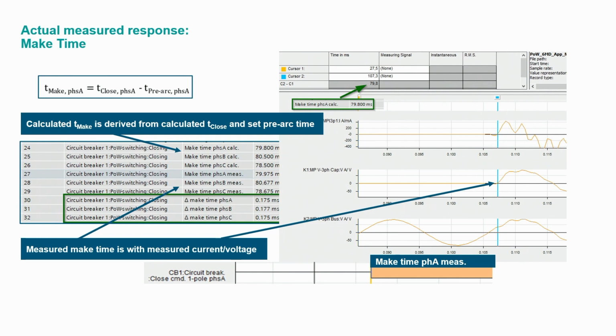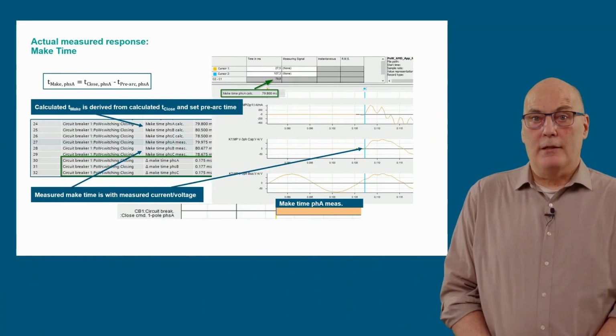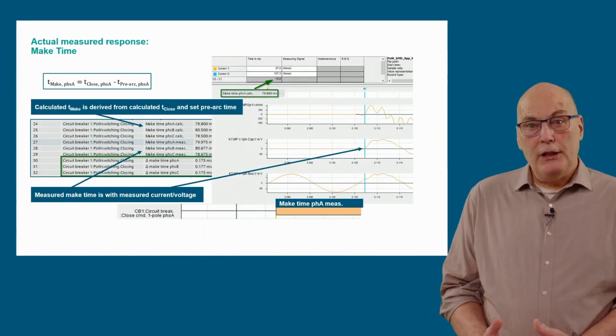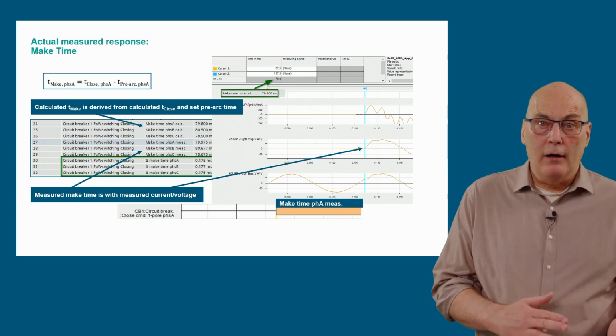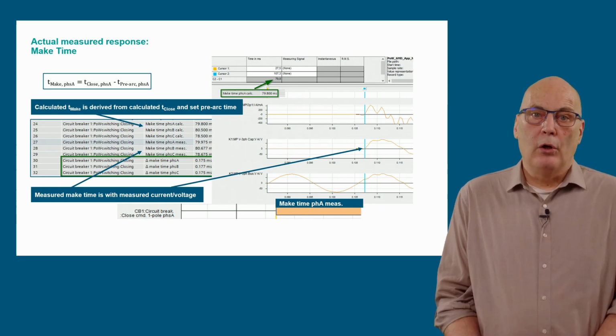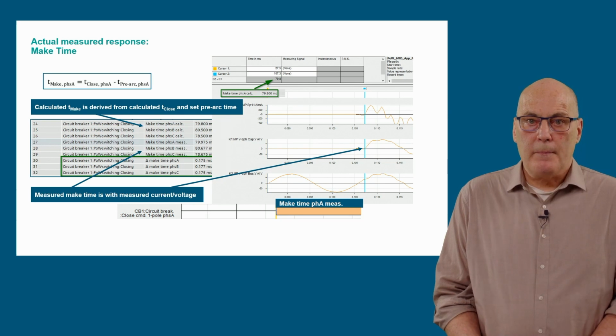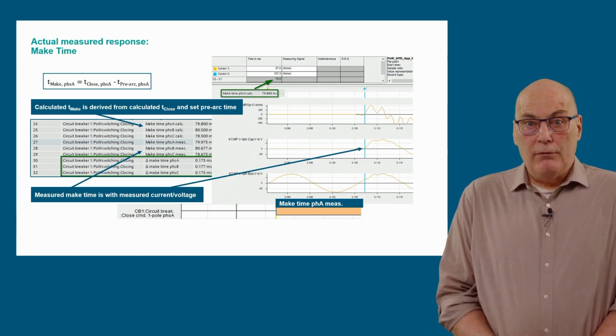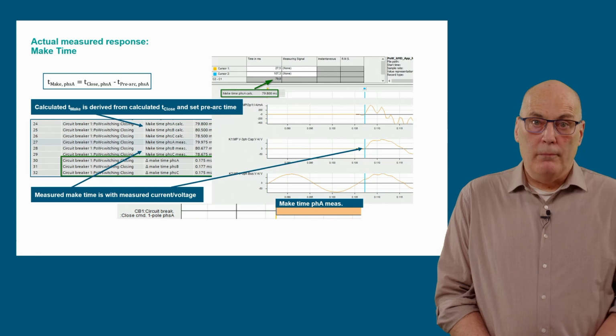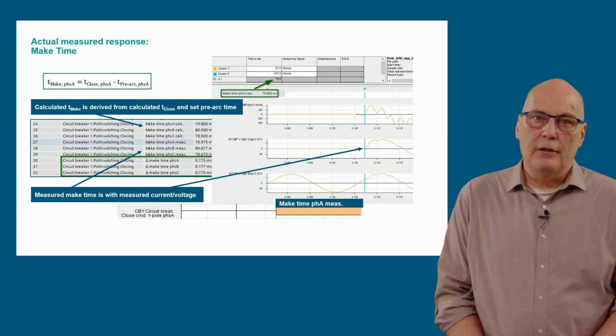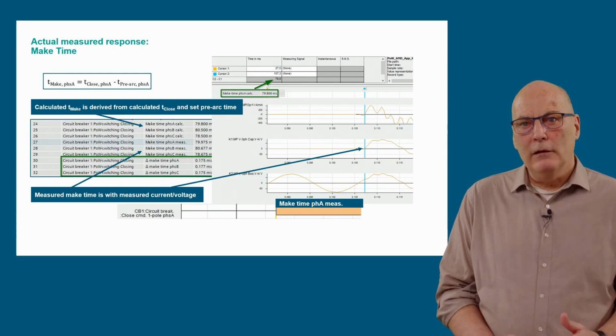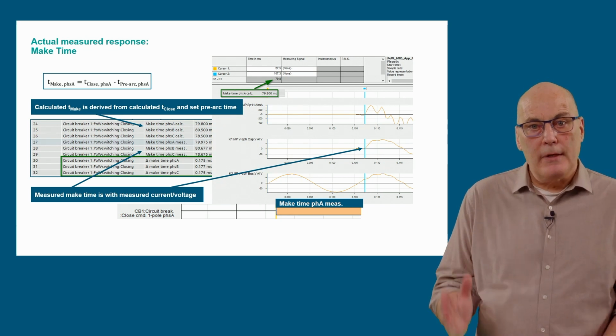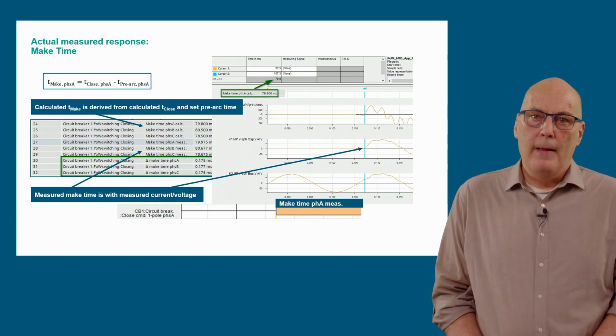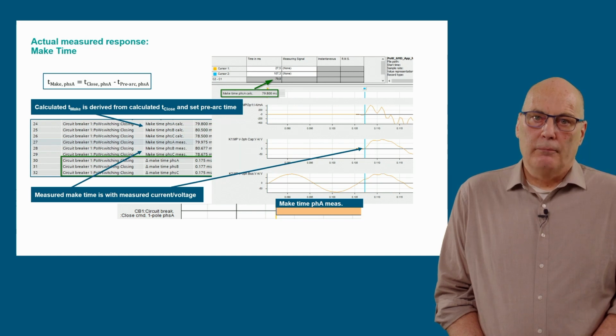The next very important value is the measured make time, for example, 79.975 milliseconds for phase A. This was measured by the point-on-wave function with a current on the load side, as shown in the diagram on the right-hand side. From the initiation of the close command, binary trace at the bottom, until current flow in phase A, that's the blue cursor in the diagram, the make time is measured.